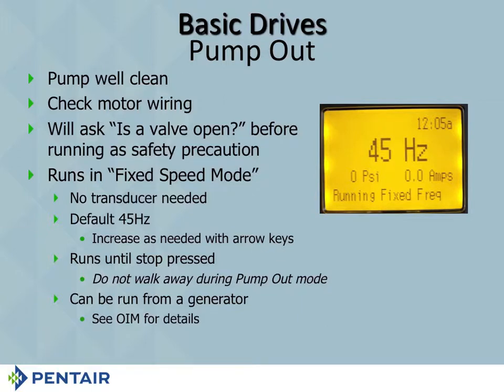When it turns on, you're going to notice that it's going to go to 45 hertz. Now, there's a reason why we pick 45 hertz, because unless you have extremely oversized the pump in the well, 45 hertz should not cause upthrust on the motor, and you shouldn't have a problem. You can change it. All you have to do is push enter. A black box appears around the 5. You can go up or down from there.